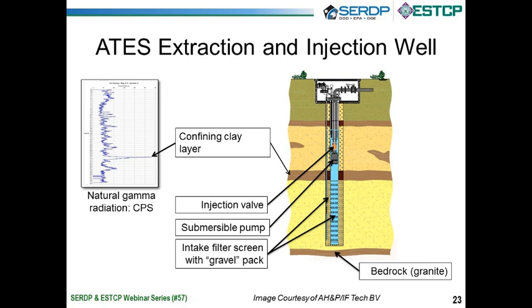So this is a conventional well, and just to give you a little details, if you've never seen a well, you surround the well with what's called gravel pack, which is basically an engineered sand to keep the sand in the formation from coming in. You pull water through these slots, the water goes up into a pump, and then the pump discharges the water out if we're in the supply mode.